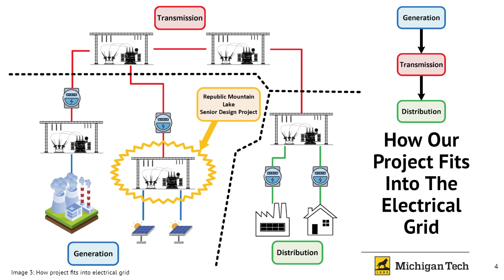Our project fits on the generation side, where we step up the voltage from the generators, which will be solar and pumped hydro, and possibly wind in our assumptions, to a higher voltage for more efficient transmission. Our project assumes around 185,000 solar panels rated at 400 watts each, producing an array size of around 74 megawatts. We are scaling this up to around a 100 MVA substation capacity to account for any other generation on site as well as future expansion.